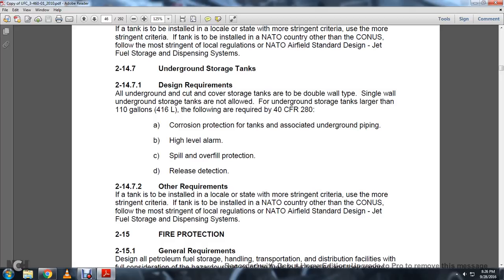2-14.7.2 The other requirements: if the tank is to be installed with local and state more stringent criteria, use the more stringent criteria. If the tank is to be installed in a NATO country other than CONUS, follow the most stringent local regulations, the NATO airfield standard design jet fuel storage dispensing system.